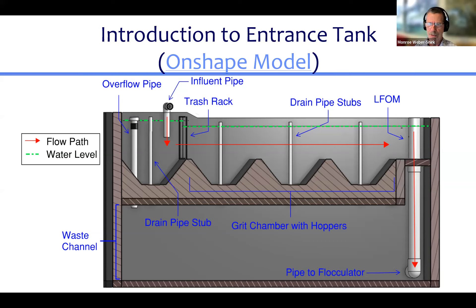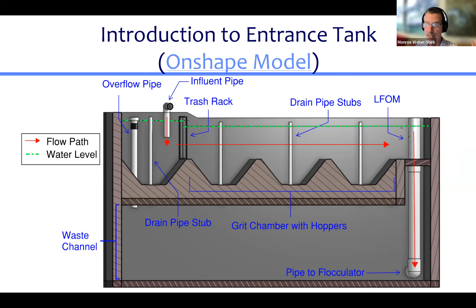There's a common confusion about what sets the flow rate in a plant - inevitably someone thinks the flow rate is based on how much water is in the river, and that if it rains a lot, more water goes through the treatment plant. That's not what happens. There's a valve somewhere in the pipeline delivering water into the plant, and the operators adjust that valve to control how much water comes in. Flow rate through the plant is controlled by a valve, not by how much water is flowing in the stream.